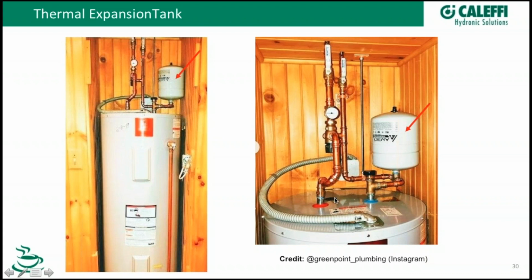And you can see one of our mixing valves here. So they're operating this tank at a higher temperature. They've got a mixing valve to mix it down to a safe temperature. Vacuum breaker here. We'll talk about that in an upcoming slide. This is a really nice installation. You've got some unistrut in there, support and all that, really professionally done. So thanks to Greenpoint for that nice work and sharing it also.